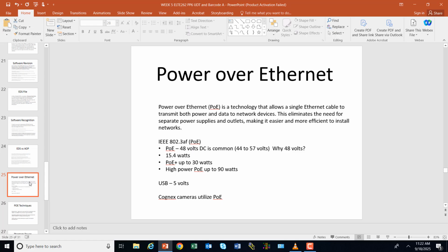Now this is good and bad. This can get you in trouble because you can have power coming over your cable, and your device might not want it. That's something I was talking about with the old 503 processors. If you plug power over Ethernet into a 503 controller, just because it's got an RJ45 on the end of it, you're going to blow that controller up, because that's a serial communication.